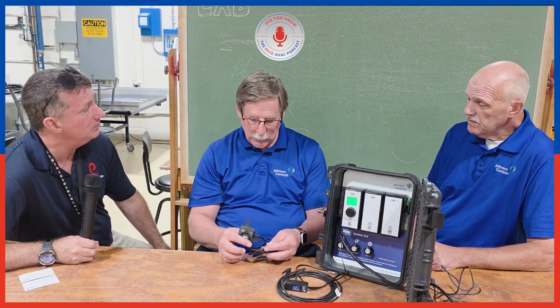There's been a lot of miscommunication amongst technicians, not understanding that these sensors have a life expectancy typical of the equipment. Some of our better sensors, I know this one very well, I've been studying the different types of technology we're using, and it really has been a very accurate sensor. The whole communication component, where the sensor knows its life and can give us those alarms, really simplifies the maintenance side.